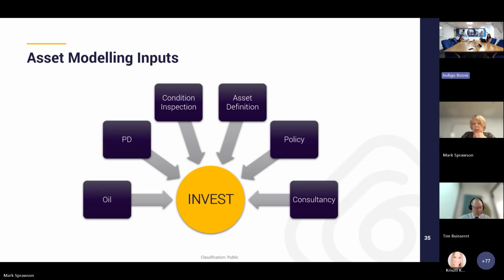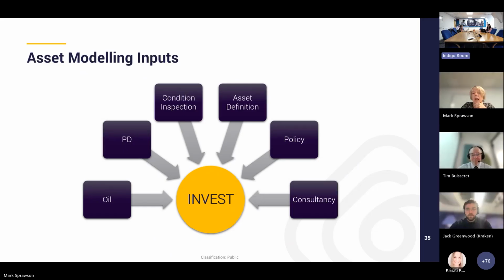That can be visual inspection data and also measured data for transformers and switchgear. Partial discharge results are particularly useful, and oil analysis results for transformers as well, because these are good indicators of asset degradation and help forecast when an asset should be intervened on.